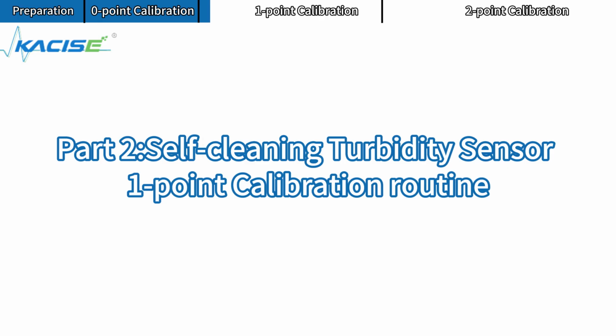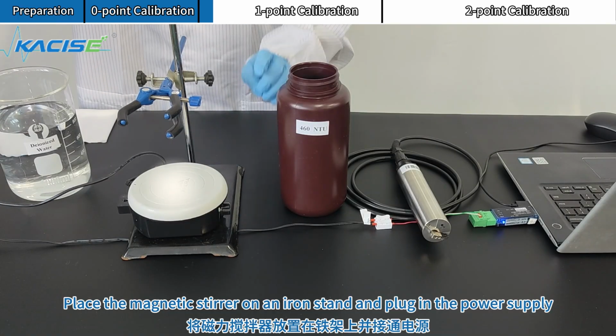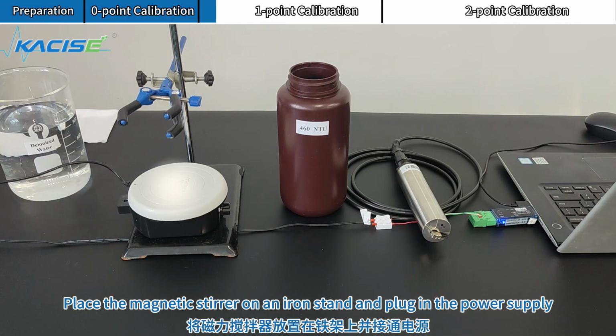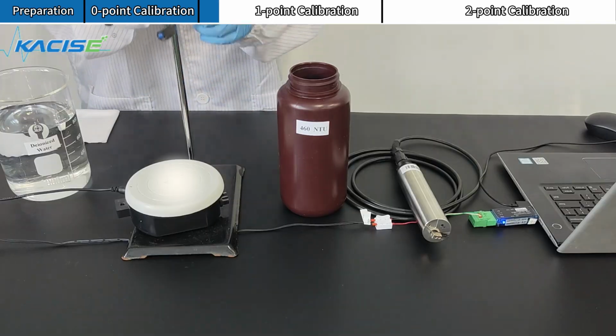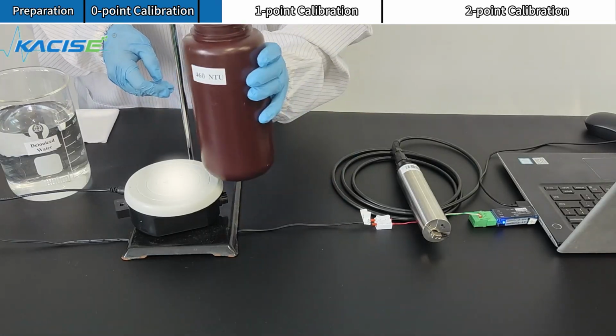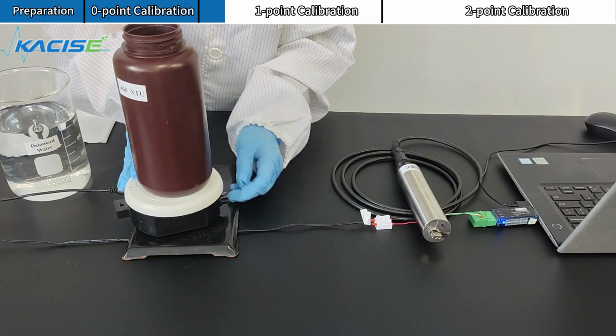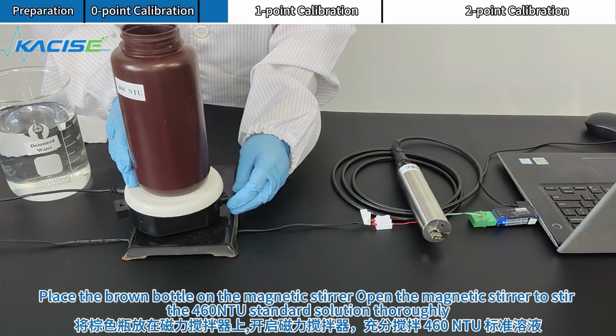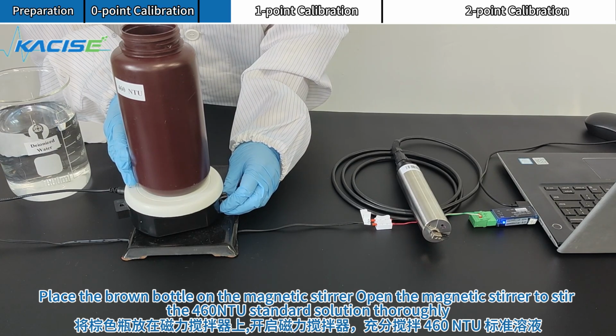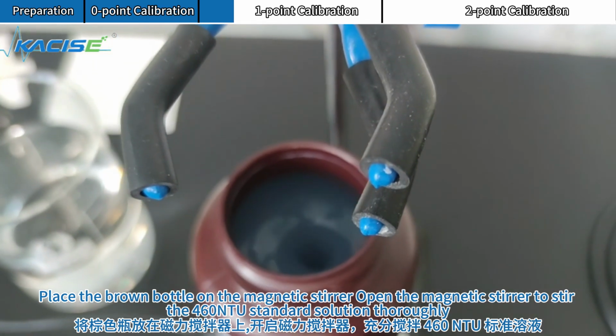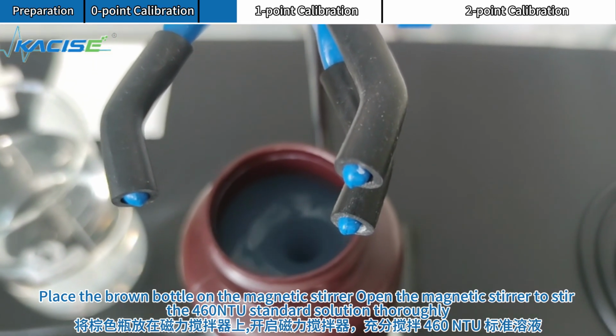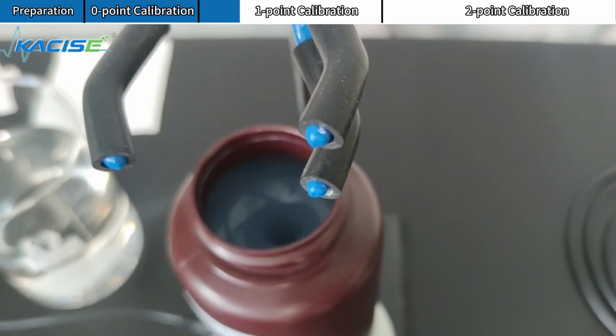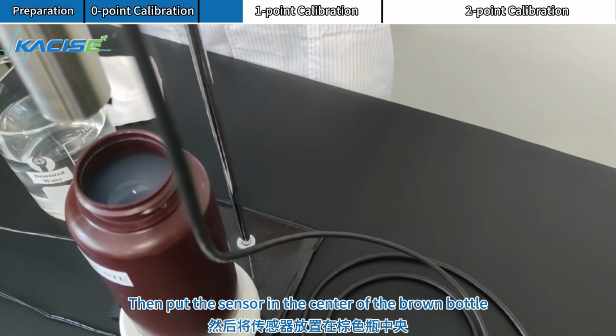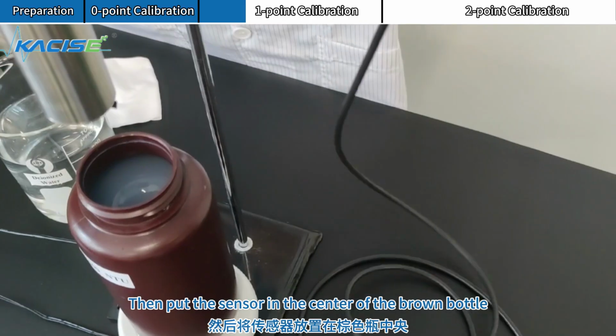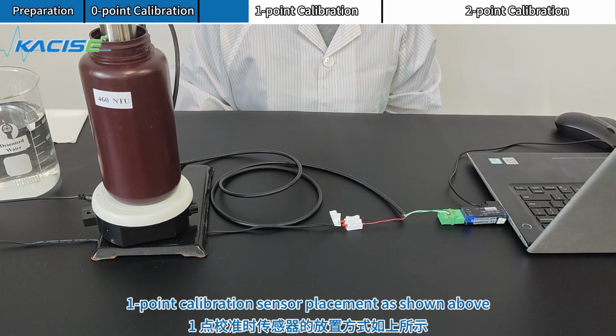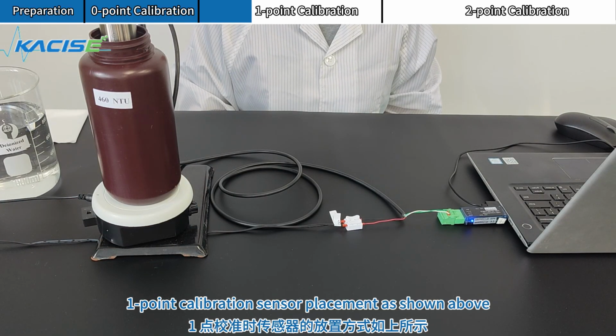1 point calibration routine. Place the magnetic stirrer on an iron stand and plug in the power supply. Place the brown bottle on the magnetic stirrer. Open the magnetic stirrer to stir the 460 NTU standard solution thoroughly. Then, put the sensor in the center of the brown bottle. 1 point calibration sensor placement as shown above.